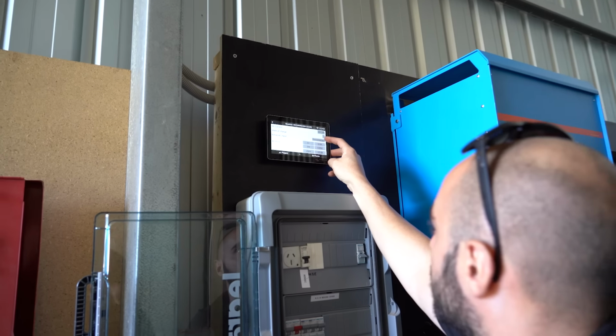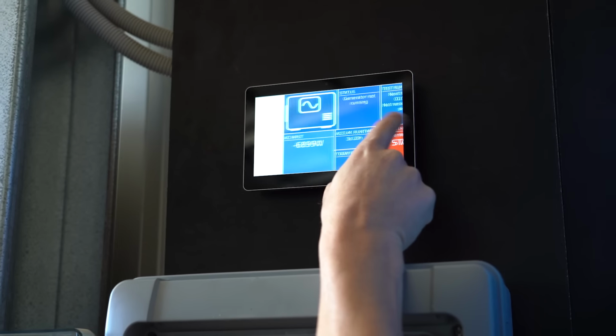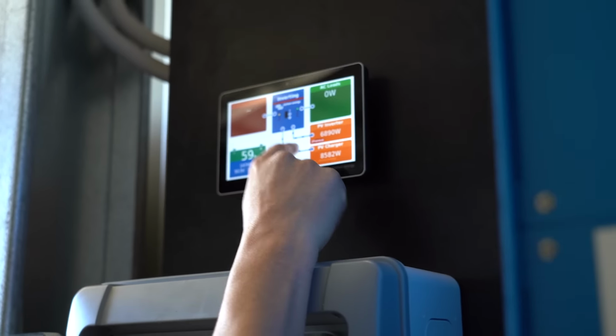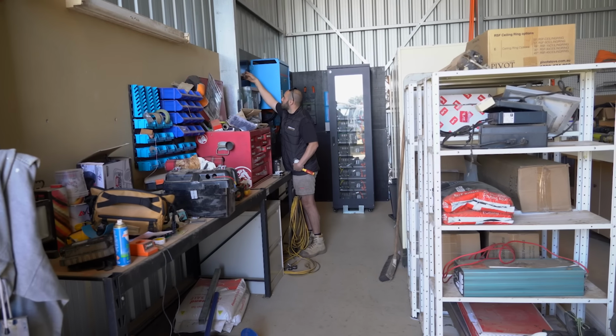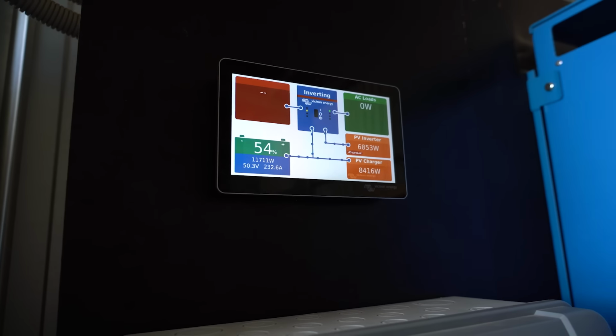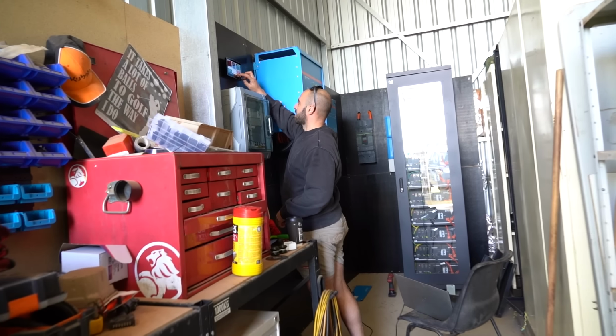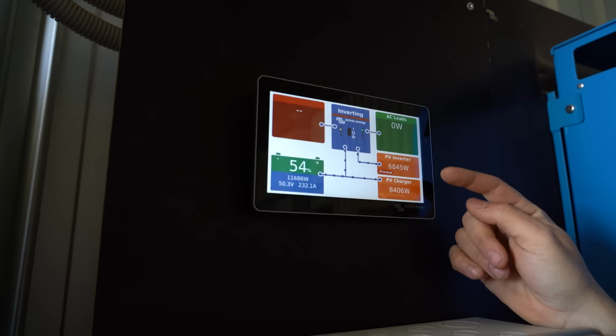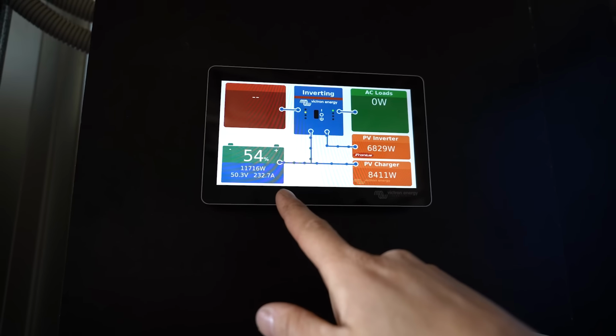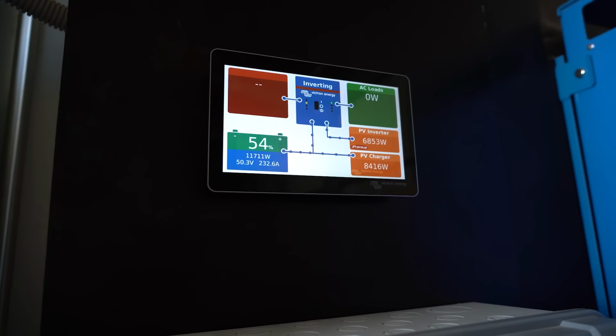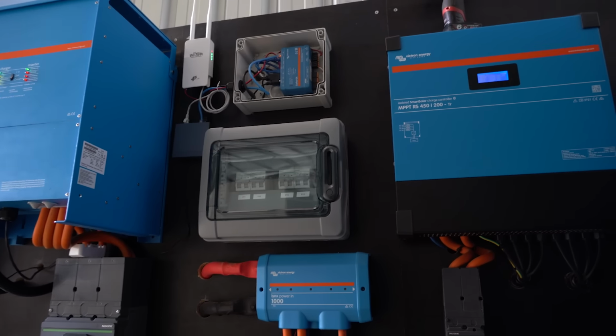We've got our GX touch controller here, so this is where we're going to see basically what's happening in our system. Right now we can see about 8 kilowatts coming in from our DC coupled charging, our MPPT on the PV charger, and just shy of 7 kilowatts coming from the Fronius. We're all feeding the battery here because we're offsetting a bit of the AC loads from the house.